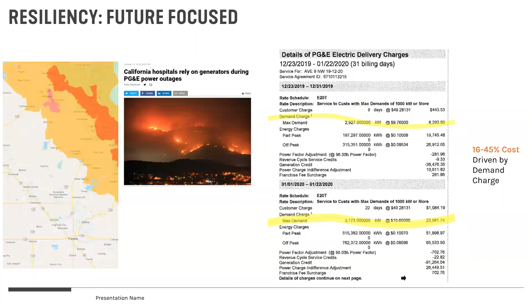But there has to be another mechanism. So we do a lot of analysis around our clients' utility bills when thinking about electrification and energy storage. There's a thing called a demand charge — it's not little, it can be about half the bill for a large hospital or lab, upwards of 40% of their cost of power. That demand charge is shown on the graph on the left: every 15 minutes throughout a month, they check what increment you used the most power in, and charge you a ton of money for that amount. If you can flatten that out and get rid of the spikes in your energy use, you can often cut the energy bill of a large entity by 30%, which is huge — we're talking hundreds of thousands of dollars of savings a year for a hospital.